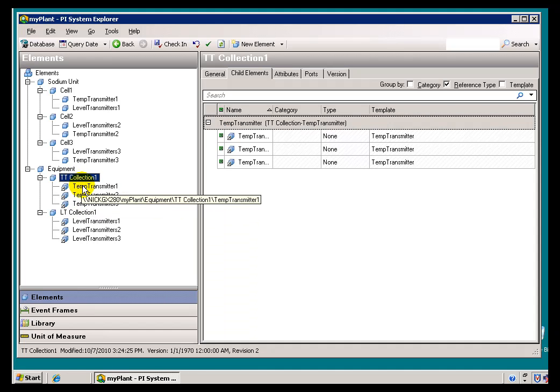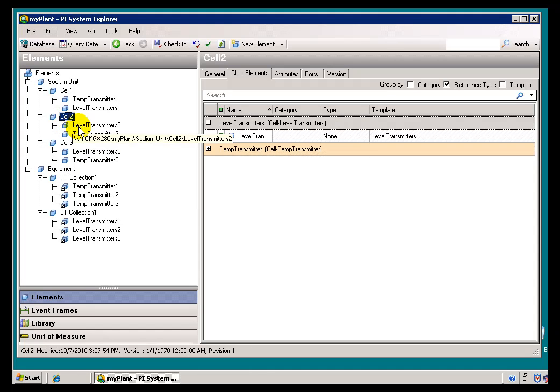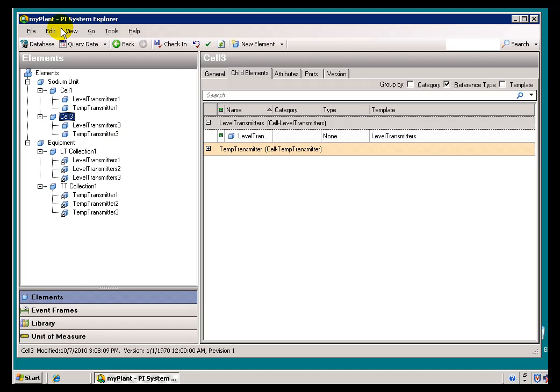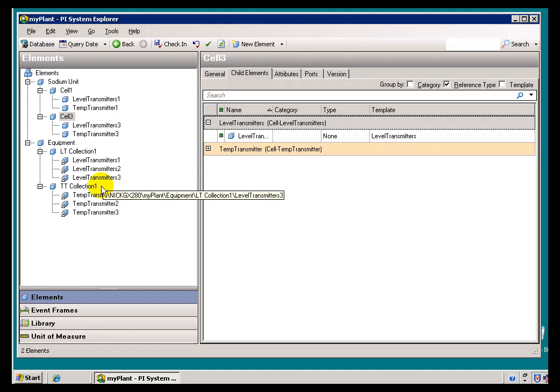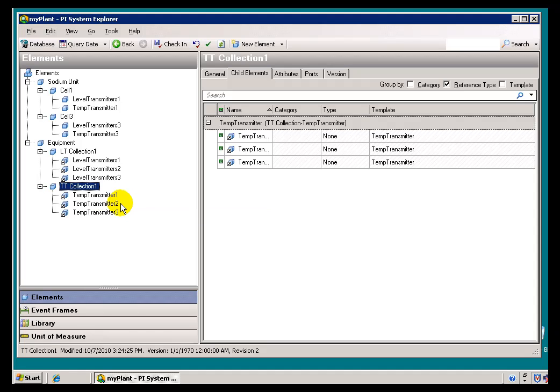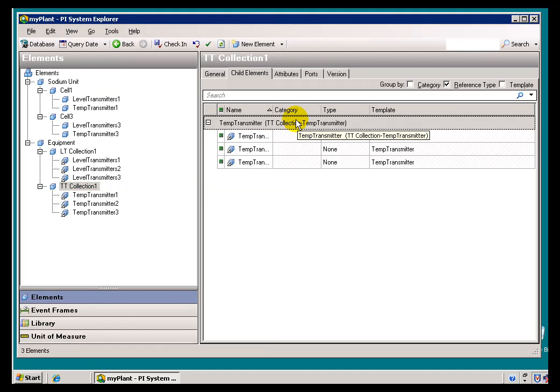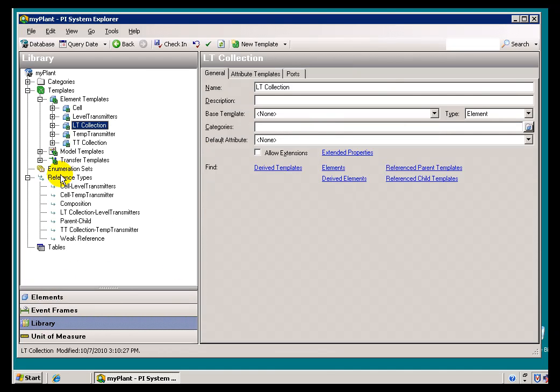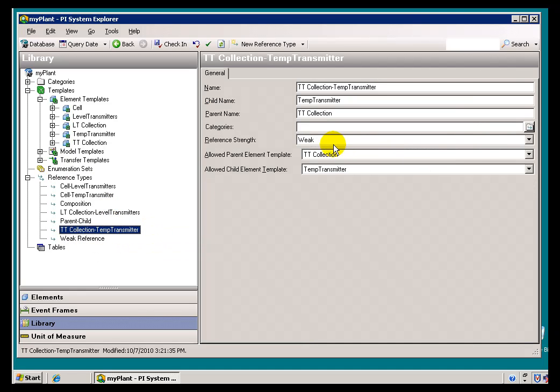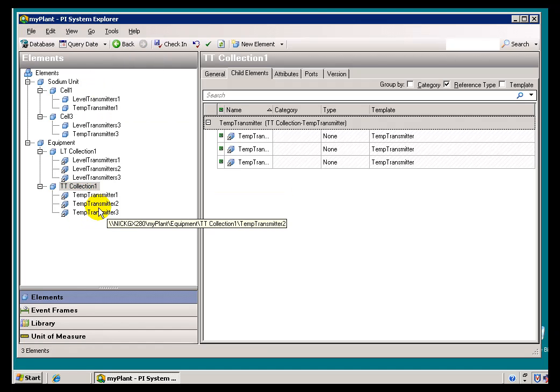Because this Reference Type relationship is weak, that means if I delete Cell 2 — I'll go ahead and do that right now — watch what happens. It doesn't happen right away, but after a little while, because Cell 2 is deleted and because this Temperature Transmitter's relationship to this Collection is a weak relationship, after the cleanup process runs — and it runs on a cycle — we're simply going to throw this Element away. I'll keep refreshing until we see that change. I want to double check and make sure that the TT Collection to Temp Transmitter relationship is a weak connection, so I'll go into Reference Types and confirm — yes, the Reference Strength is weak.